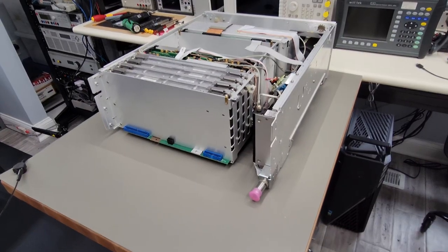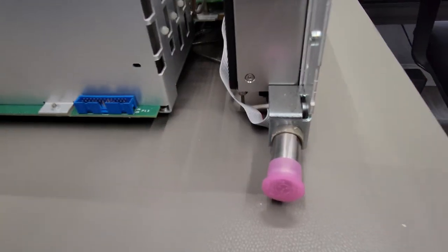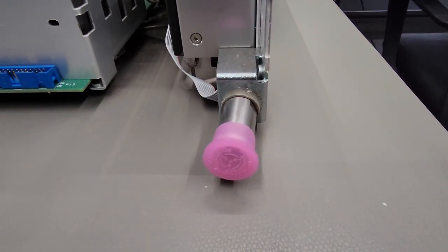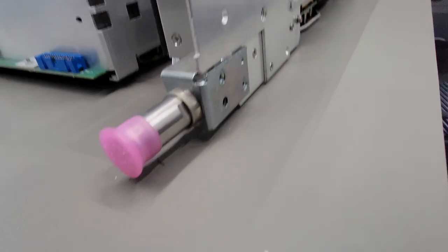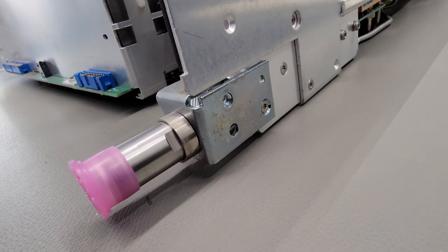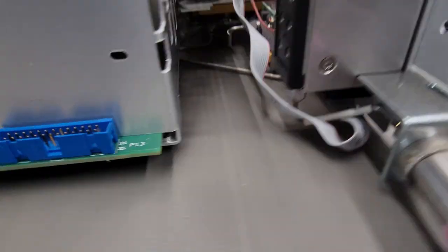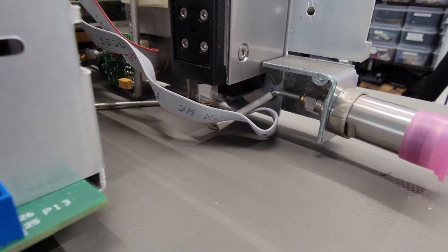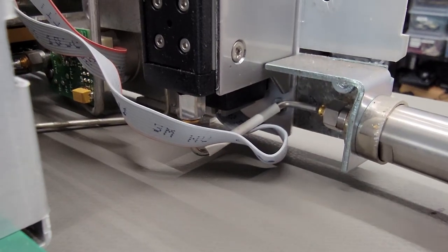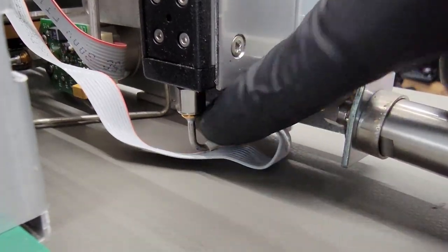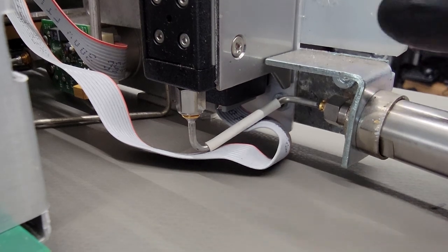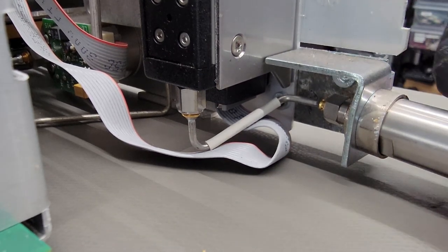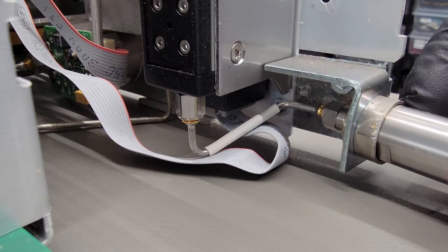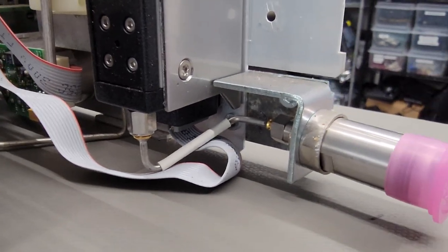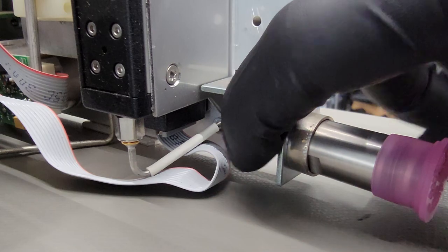All right, so just showing some details here on the front panel RF connector assembly. We have the connector itself and the mounting bracket that holds it to the chassis. You can already see how it's bent out of shape here. And then if we look on the inside, you can see the semi-rigid cable that connects straight to the attenuator. So what we can do now that we have access here is to begin breaking this assembly down and testing the individual components to see if that has anything to do with our loss of amplitude at the output of the instrument, or if we need to look further.